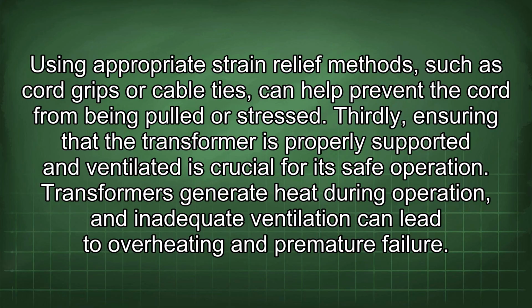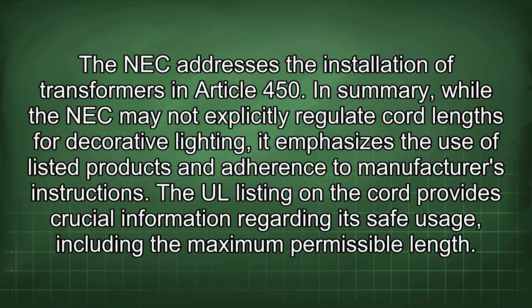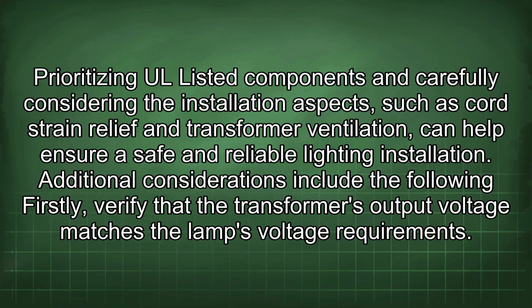Transformers generate heat during operation, and inadequate ventilation can lead to overheating and premature failure. The NEC addresses the installation of transformers in Article 450. In summary, while the NEC may not explicitly regulate cord lengths for decorative lighting, it emphasizes the use of listed products and adherence to manufacturers' instructions. The UL listing on the cord provides crucial information regarding its safe usage, including the maximum permissible length. Prioritizing UL-listed components and carefully considering the installation aspects such as cord strain relief and transformer ventilation can help ensure a safe and reliable lighting installation.